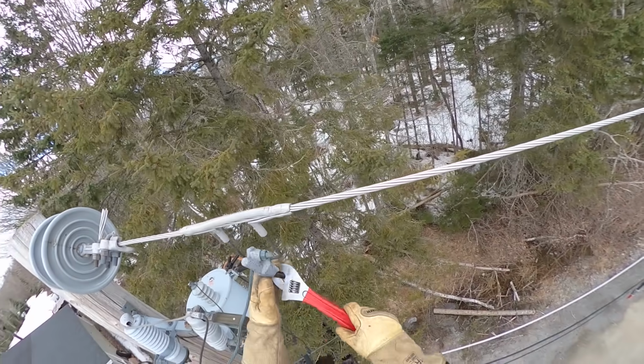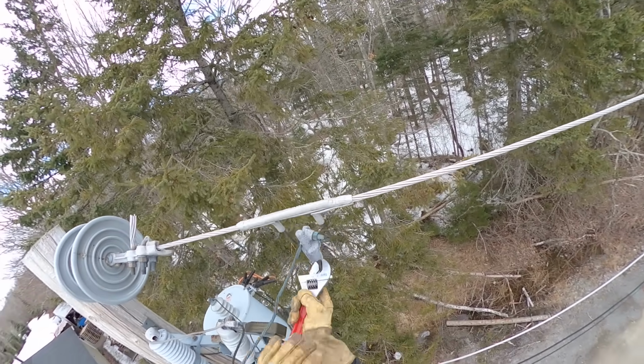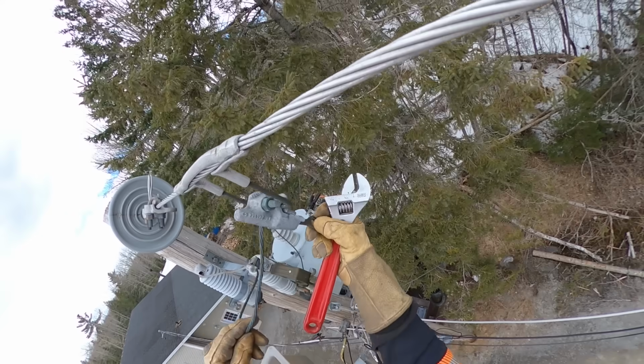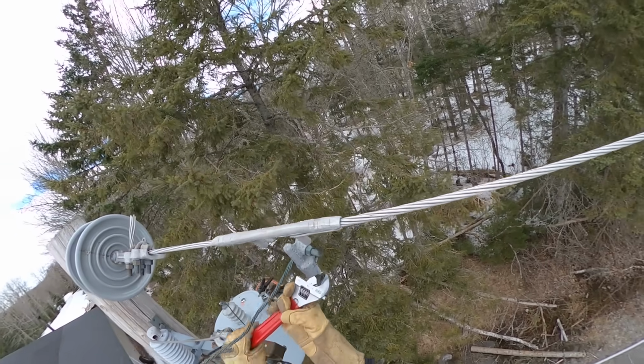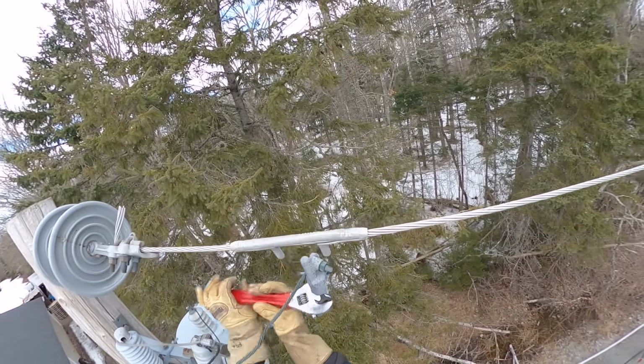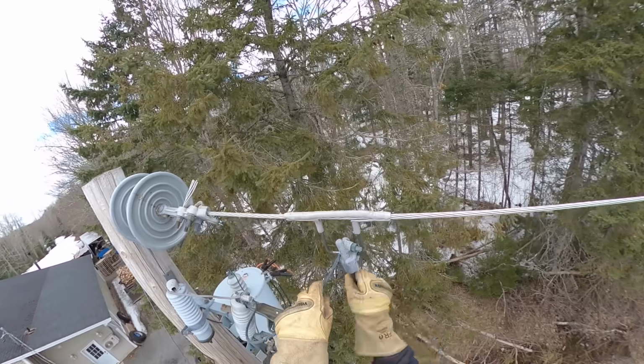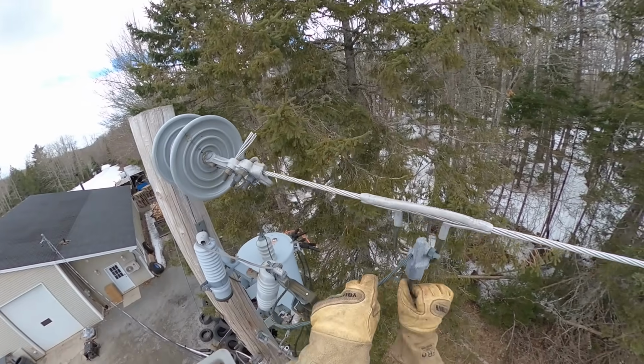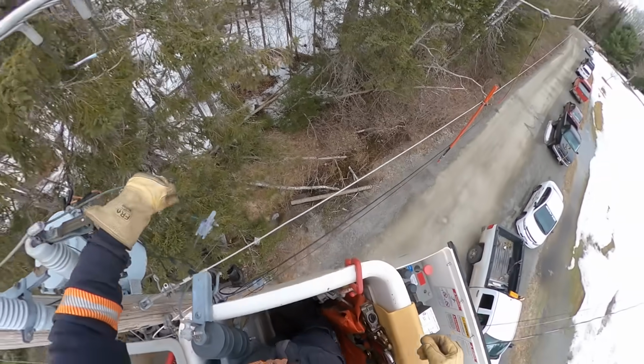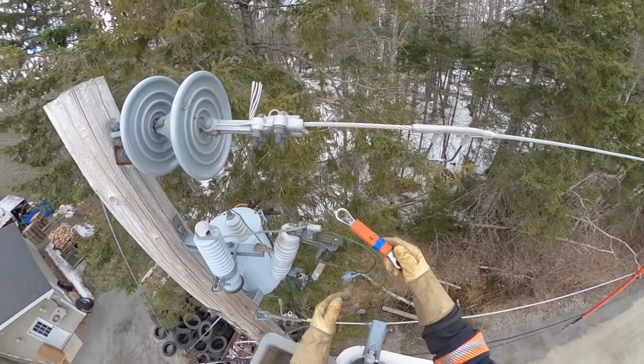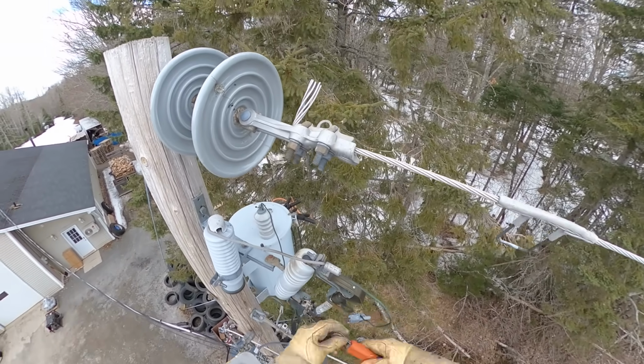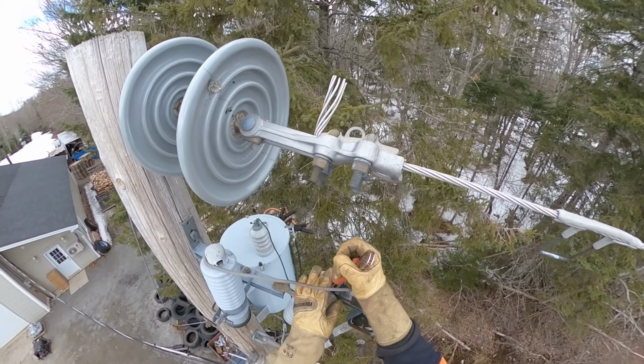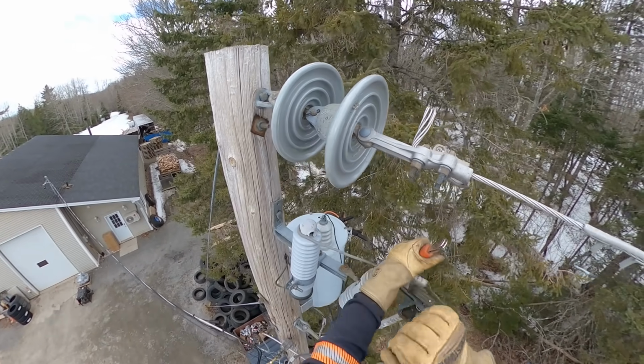So first thing we're going to do, this tap clamp, it wasn't on very tight, and it's actually kind of seized up. It happens once they get old. I imagine there was a little bit of arcing in that tap clamp. We gotta strip it off anyways, just to change out when we resag that primary. You don't want to leave that tapped on. You can actually even see some corrosion on that stirrup on the primary, that little bit of a white color there. In fact, everything up here is seized on pretty good.